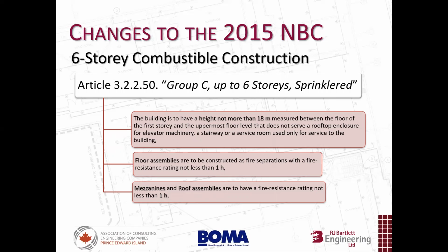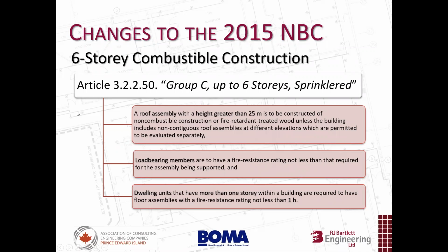This roof assembly requirement is not typical for sprinklered buildings. So this is another enhanced measure that's required for this mid-rise construction, to have the roof assemblies rated as well. And roof assemblies, if they have a height greater than 25 meters, need to be of non-combustible construction or fire-retardant treated wood. If the building has different layers, then these sections of the roof are permitted to be treated differently. And the ones that I've been working on have all been flat roof structures.